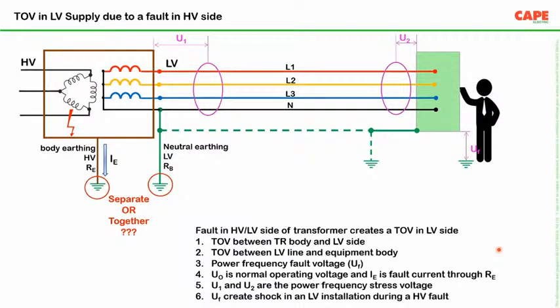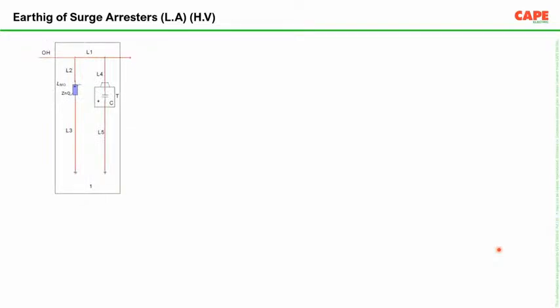So, but I would pinpoint that these three, the purple color, U1, U2 and UF, these are the voltages which you are supposed to take care. Now, one interesting subject is the earthing of surge arresters in high voltage. What I am showing is that T stands for a transformer. You have L1, the line, L2, the line between the line and the surge arrestor, which is the zinc oxide arrestor, and L3 from the surge arrestor to the earth pit.